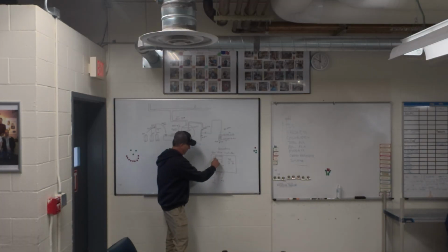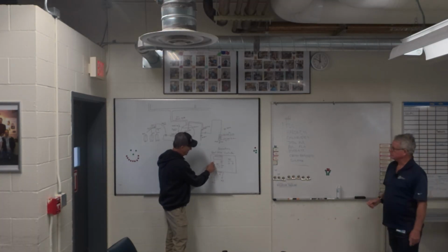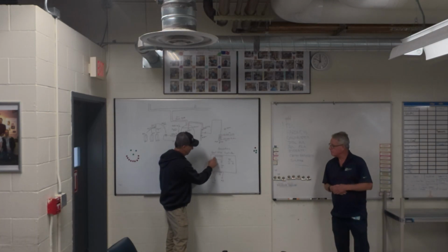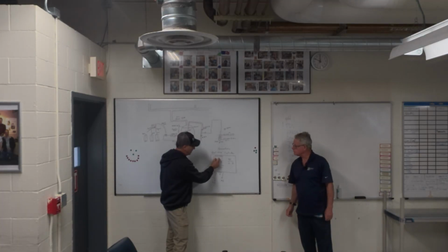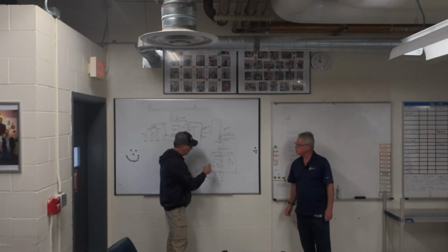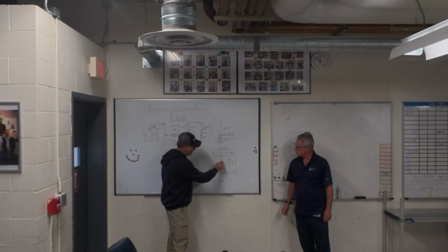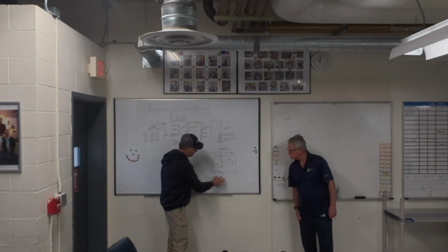I can set this controller up for every 5 seconds. When I sequence this, when I push this button, this lights up, and my display indicates the accumulation rate, and I can modulate that, dial that up or down. Then I sequence to the next one, and it's the timer. I can dial that up or down, 5 seconds, 10 seconds. And then you go on to this channel, this will light up for channel 2. Same way, like, I think every 10 gallons I want it to initiate the sequence for just 3 seconds. Okay, so you can really fine tune each channel.